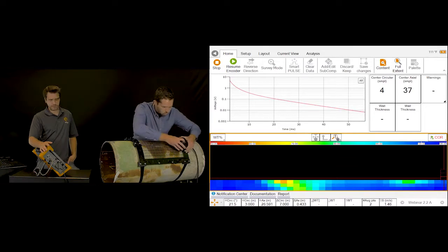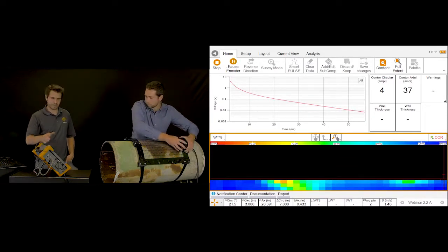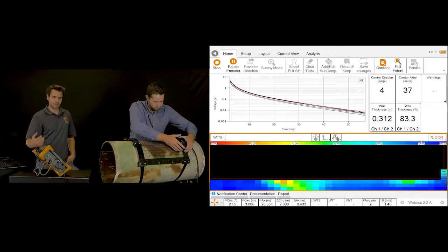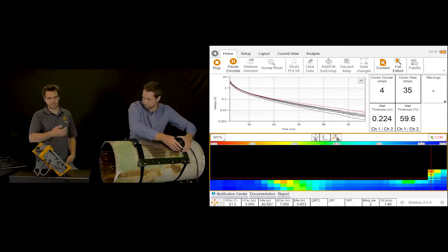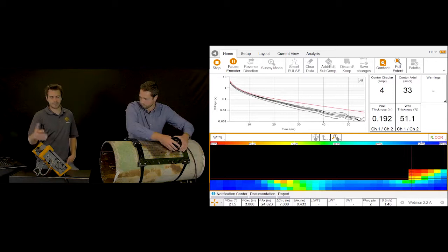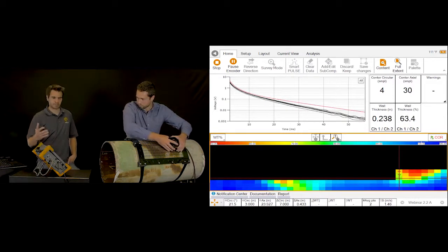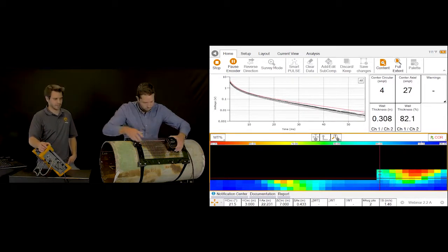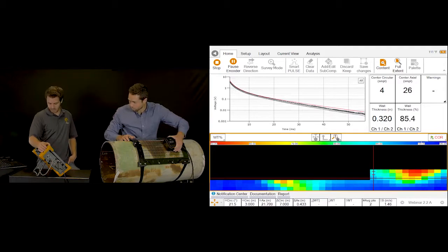LYFT is doing a unidirectional pattern scan. So this is something we introduced in the previous version. You just start at the same axial position for every line, and this gives you a C-scan which is much better aligned than if you were doing a raster scan.